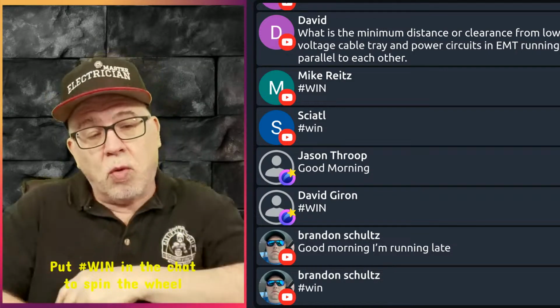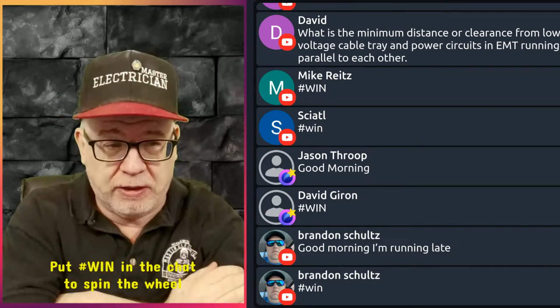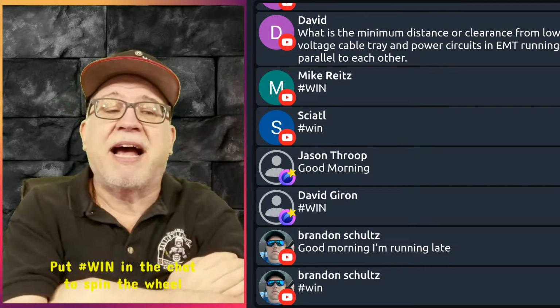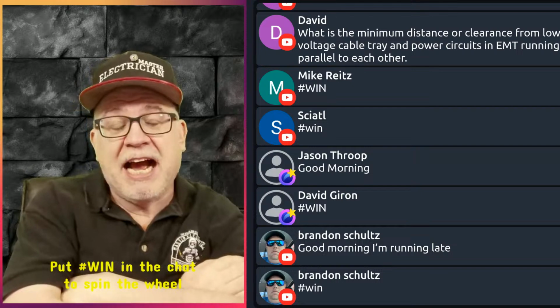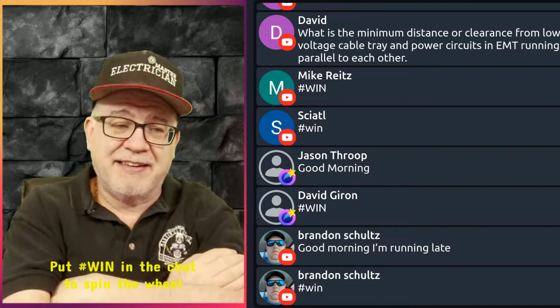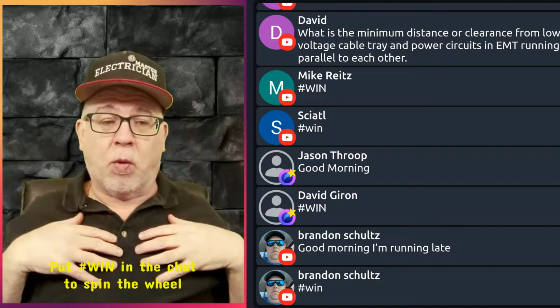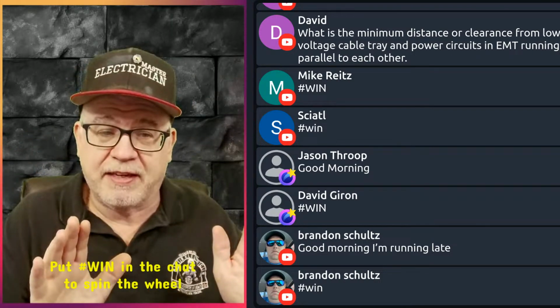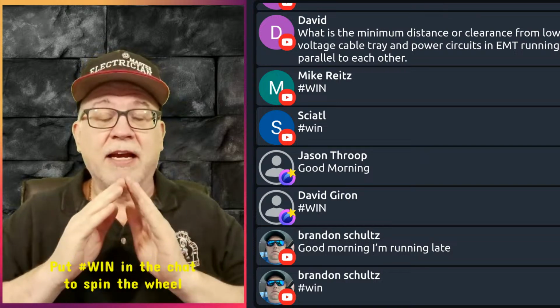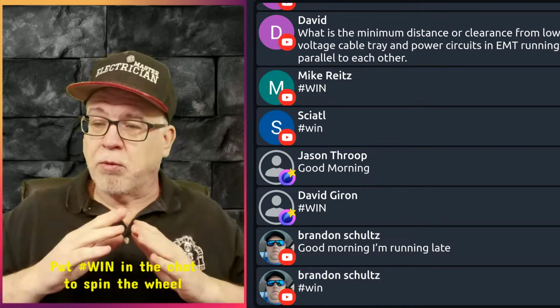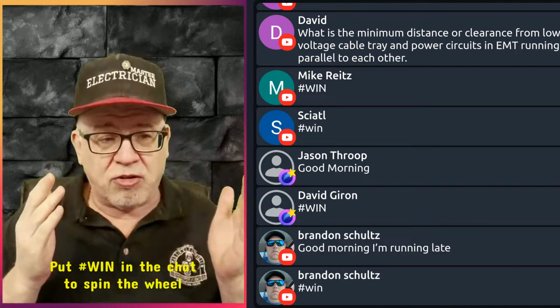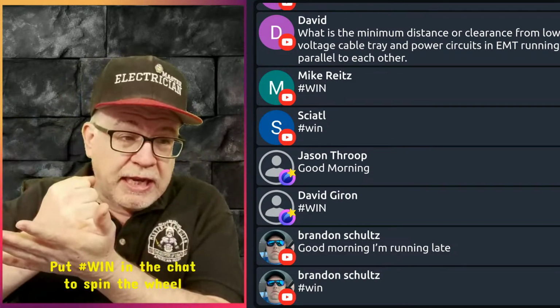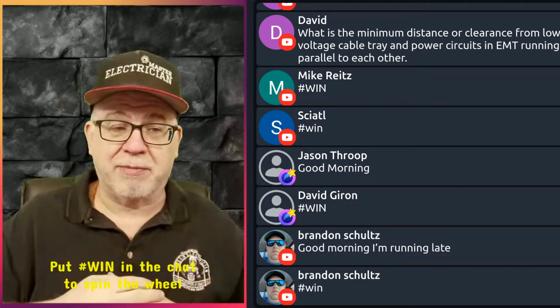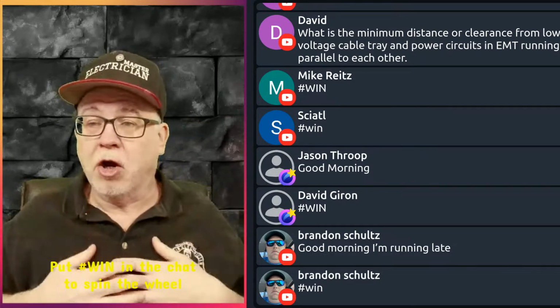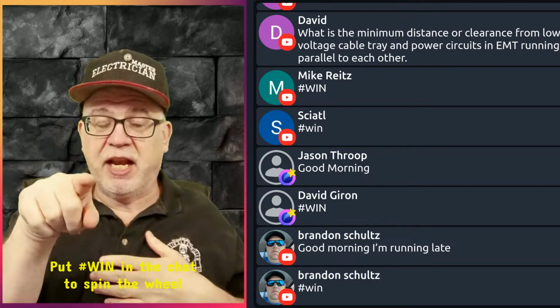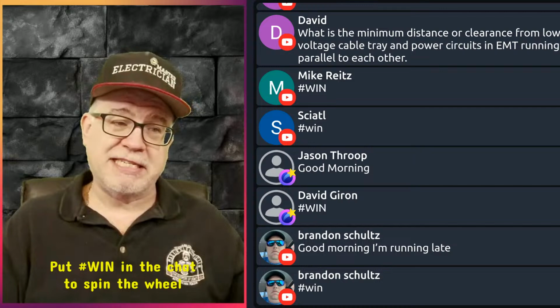So what this means is, you know what? An engineer under engineering supervision can come up with an ampacity value for these conductors that may be higher than what's given in table 310.16 for the conductor, and it doesn't matter to the manufacturers of the wire. We don't care. We like to follow 310.16, but if an engineer wants to use a kind of a Neher-McGrath type of calculation, they want to use the informative Annex B values, they want to do all that, and they're willing to put their stamp on it, we're okay with it because they're the ones that will be responsible. If something happens, the installation melts down, something fails, the manufacturer's going to go, you did it, I didn't do it. We recommend you follow 310.16.